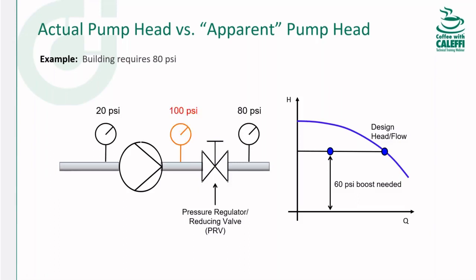The mistake I see is that people will read the tag information of the existing pumps, and the existing pump nameplate will have the head of that pump, and that's the head of the pump before it goes through the pressure regulator valve and then out to the discharge manifold. So in this case, if we were at a low flow, you would see 80 PSI in the discharge gauge. What you do not see a lot of times is the pressure between the pump outlet and the pressure regulator valve. And in this case, it's 100 PSI. So the actual pump head is 80 PSI of boost, as opposed to 60 PSI of boost.